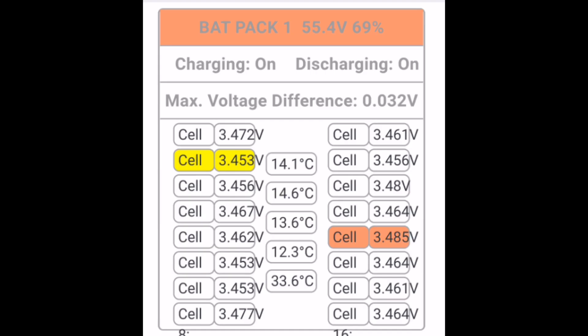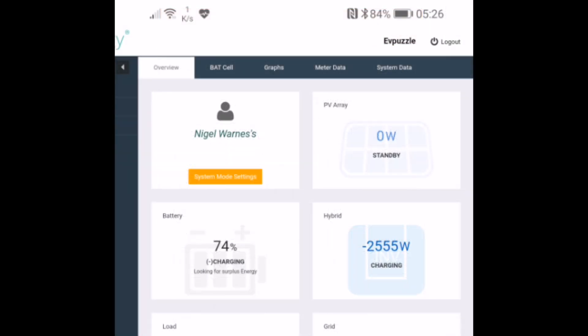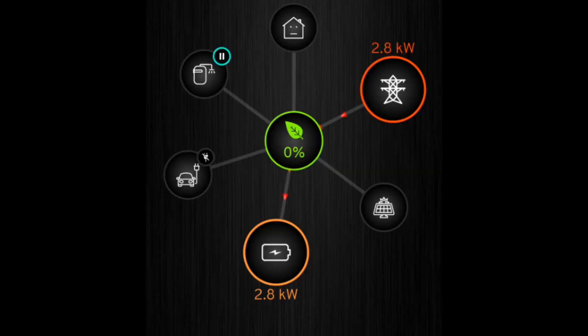Looking at the physical battery stats, we're at 69% state of charge, but we've got five temperature sensors there. One you can see at 33 degrees C, that must be the inverter. And the other four sensors are four positions inside the battery pack. And we're varying between 12 and 14 degrees C. Quick check of the time. It's 5:25 in the morning now, and we're charged back up to 74%. And we're still doing 2.8 kilowatts going into the battery.